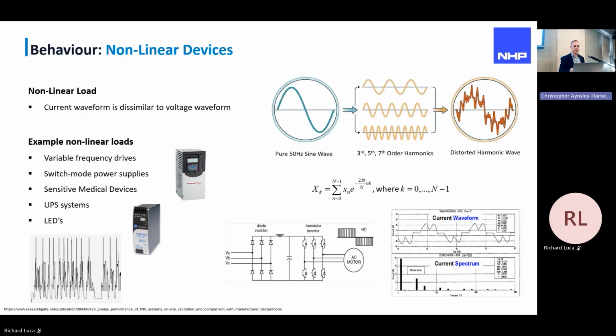And the common example there, bottom middle, is a drive schematic where you've got an input rectifier stage. So the diodes are switching, rectifying the voltage, and the current is being reproduced to control the motor. So in that rectification process, you're getting all these anomalies or harmonic distortion occurring. And you can see that in the far right there. So really distorted wave, and the harmonic spectrum, you can see the fundamental frequency, it's quite high. And then you've got these other odd orders introduced in the network.